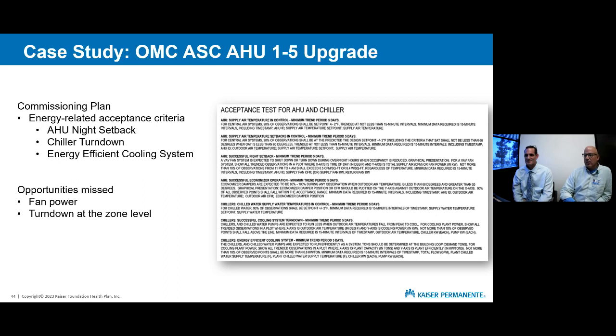An acceptance criteria for chiller turndown was included, but there was nothing in the sequence of operation that addressed that. It just ran 24/7. Right. And there was verification of an energy efficient cooling system. They set a target, and I think it was about 0.8 kW per ton. Right. Nothing on turn down, fan power.